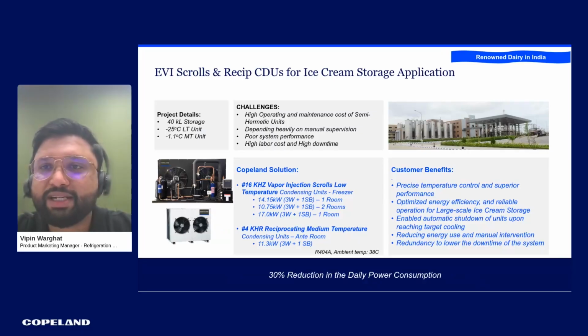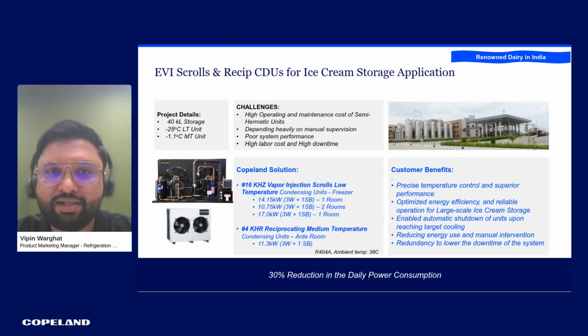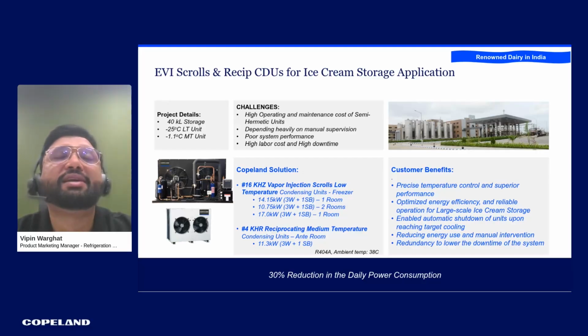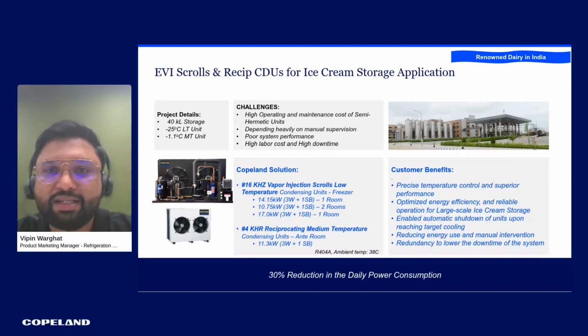Similar to the food retail application, we also supplied similar equipment, that is a vapor injection based condensing unit, for a higher capacity cold storage application, which is 40 kiloliters of ice cream storage. As you see on the screen, there were 16 units delivered. Earlier, the customer was using reciprocating technology, mainly semi-hermetic, and against that it was evident that they were able to see the benefit by a reduction of 30% in their daily power consumption. So this is the amount of savings and value this vapor injection scroll can deliver. So if we move on.